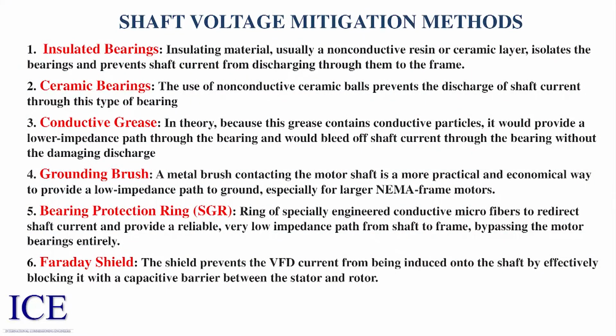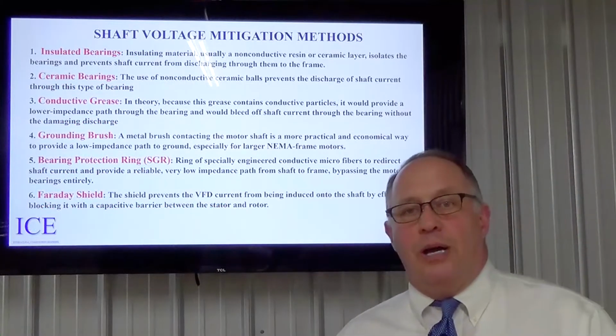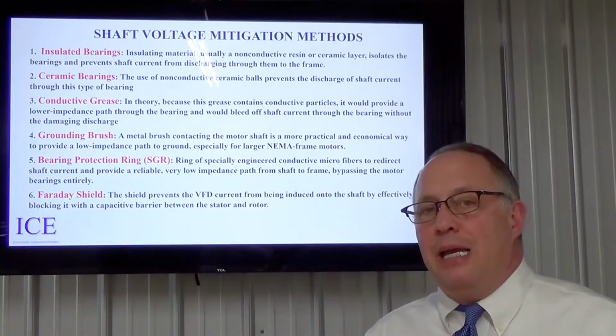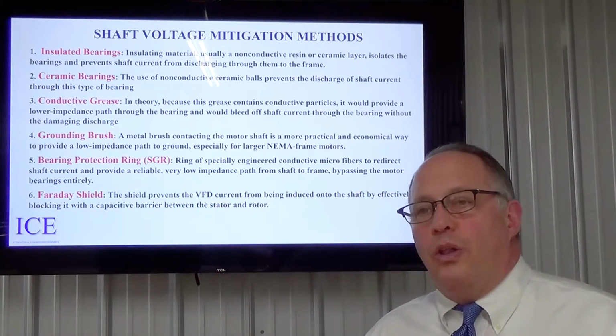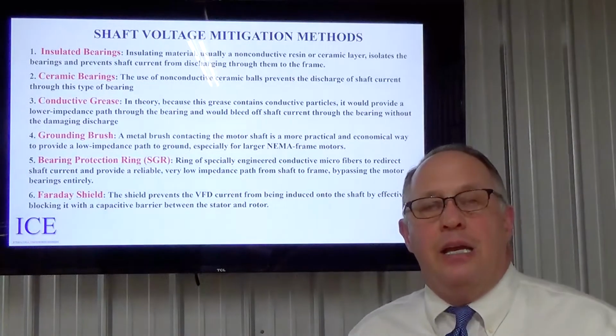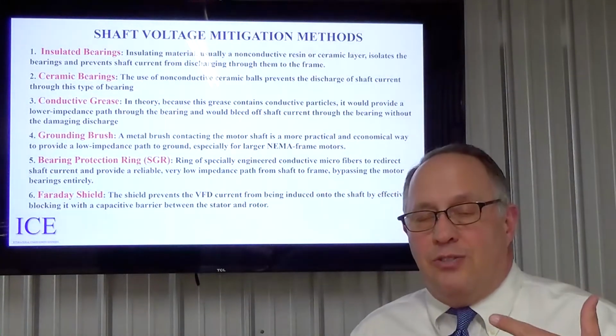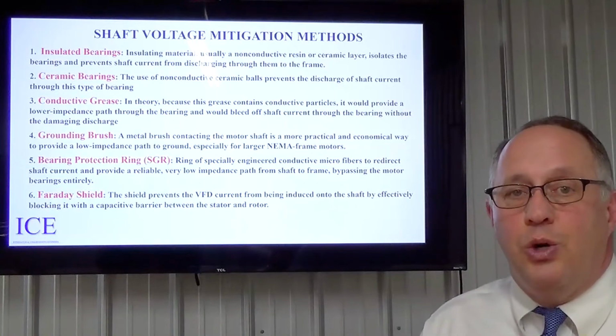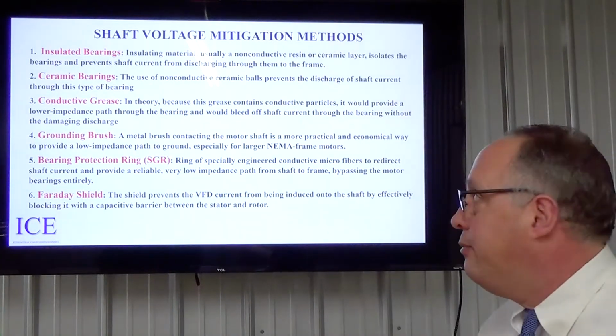Number 6, a Faraday shield. This shield prevents VFD current from being induced onto the shaft by effectively blocking it with a capacitive barrier between the stator and the rotor. Certainly an effective way. You've eliminated any ability for the capacitive effect that we need using this Faraday shield. Expensive way to do it. Does it work? Absolutely.